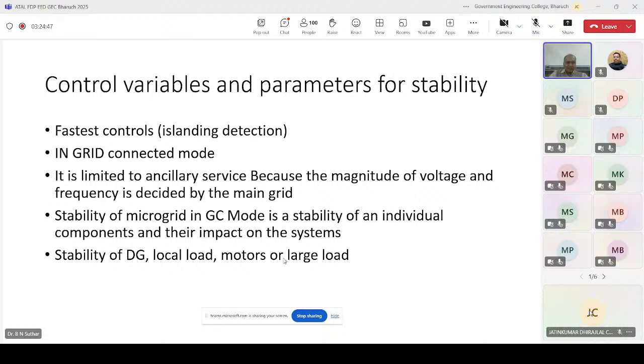So you cannot do anything to the stability of the grid. It will run in its own way. But when you talk about the stability of the microgrid, it is the local stability of the local equipment. So local or individual components in the microgrid will decide the stability of the microgrid when it is connected in the grid connected mode. So it is basically the stability of distributed generations, local loads, motors or large loads, whatever is there in the grid.